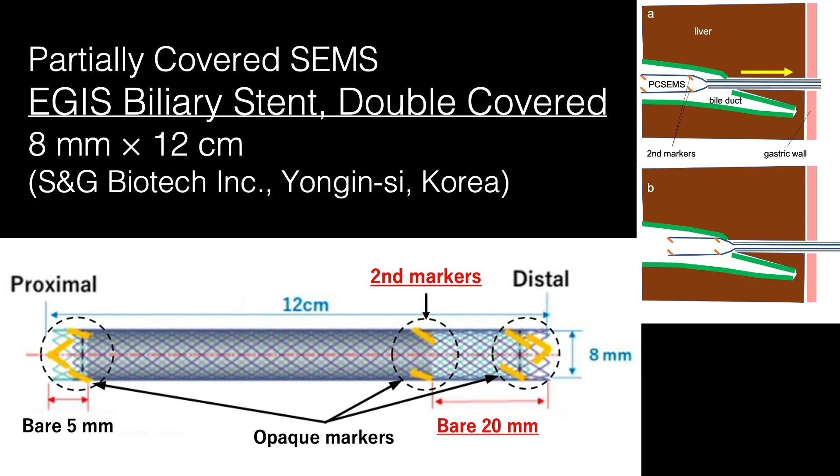Recently, a novel partially-covered metal stent with a 20 mm distal bare portion has been developed to avoid blocking biliary side branches. This stent has radio-opaque markers located at three positions. The second marker, located at the junction of the bare and covered portions, 20 mm away from the distal end, assists with stent deployment.